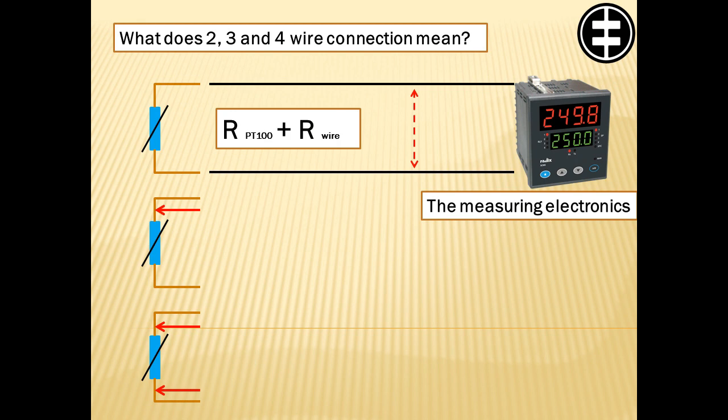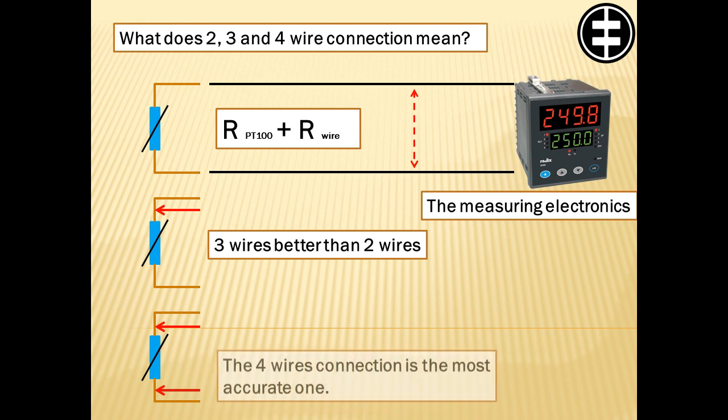Using extra wires for compensating the cable resistance gives more precisely the desired resistance of the RTD itself. The 4 wires connection is the most accurate one.